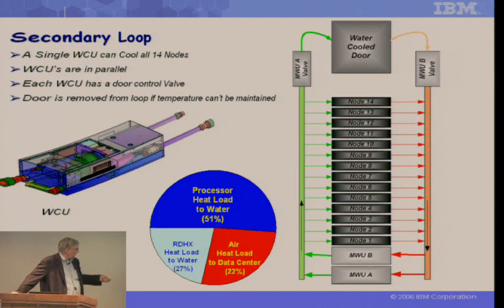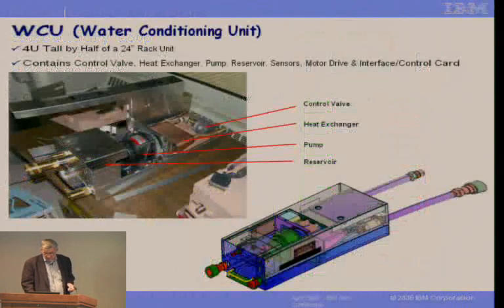So here's how the heat load is taken out. The processor is about half the heat load. The rear door heat exchanger on the back takes about 27%, and what's remaining, about 20%, goes out into the room. Here's the water cooling unit, and I'll talk a minute about that. The next one.